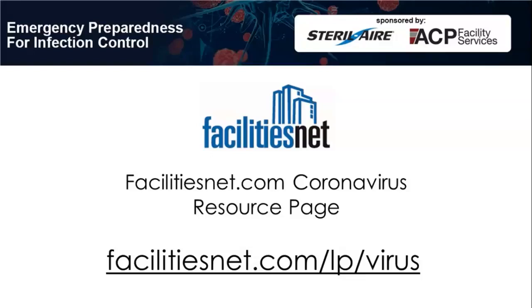So these biofilms are basically a breeding ground for antibiotic resistance, and they also cause mechanical issues. If it's on a cooling coil, it's 1,000 times less effective at transferring energy. So UVGI is incredibly effective at removing biofilms. We just have to gear our disinfection to what's actually in those, and mostly it's mold-based organisms that we need to disinfect.